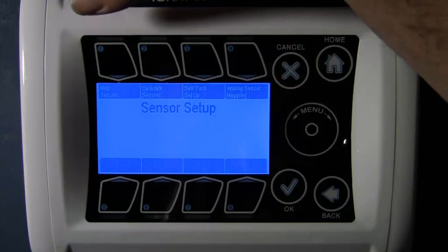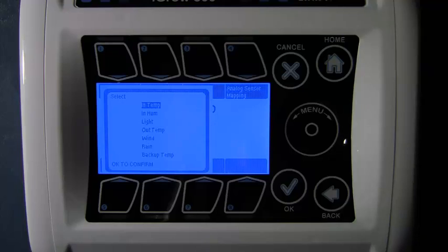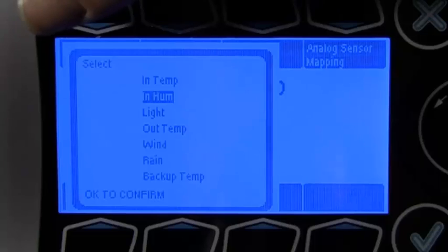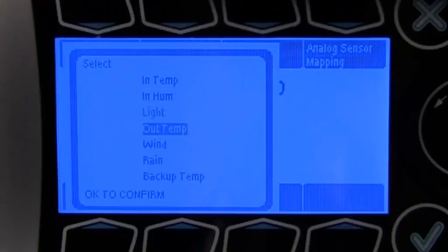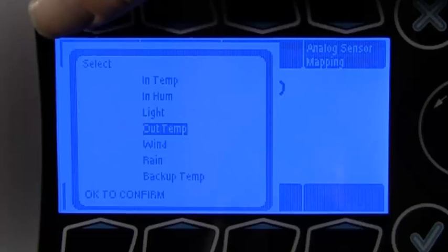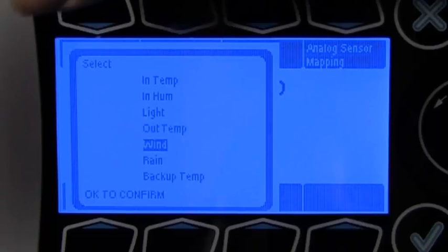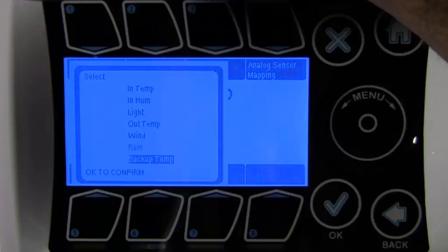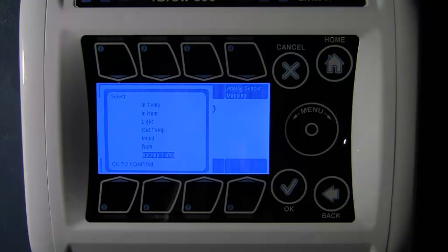But first, let's go ahead and go into Map Sensors. And in this field, you have several different sensors that you can map. You can select from inside temperature, inside humidity, light sensor, outside temperature sensor, wind direction and speed sensor, the rain sensor, and finally, backup temperature sensor. Note that all sensors by default are disabled until you enable them or assign them to respond to software.